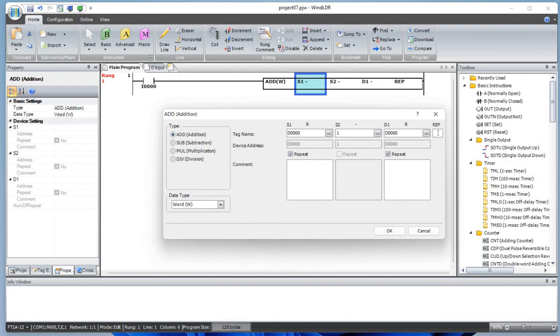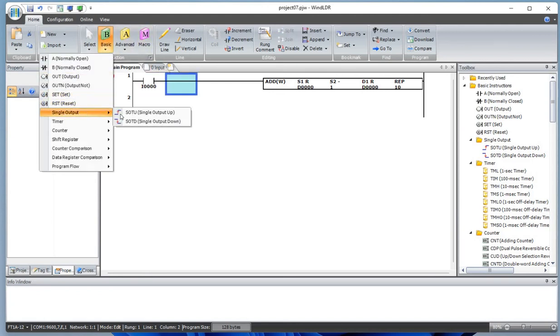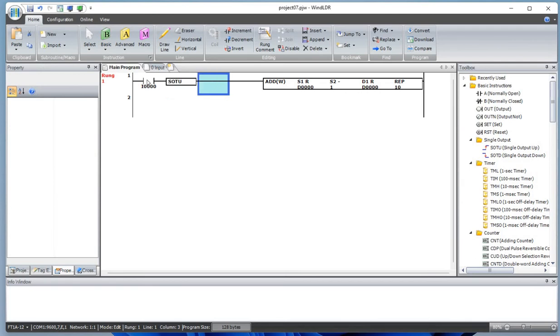Basically we are making a counter — adding one to data register D0 and saving it back to D0. Let's add a single output up trigger (SOTU) here. When the output turns on, this will count once. When it's off it does nothing, and when it turns on again it counts one more.